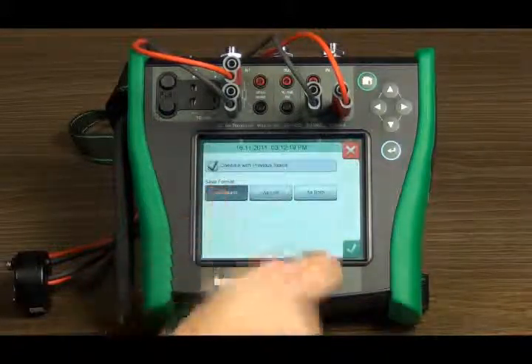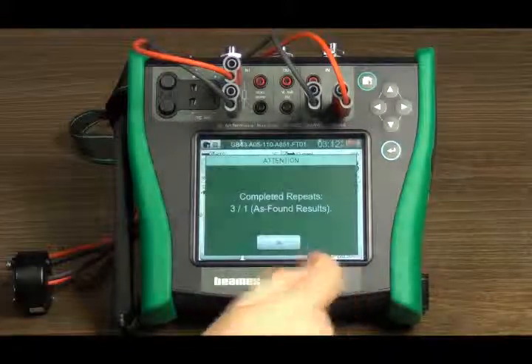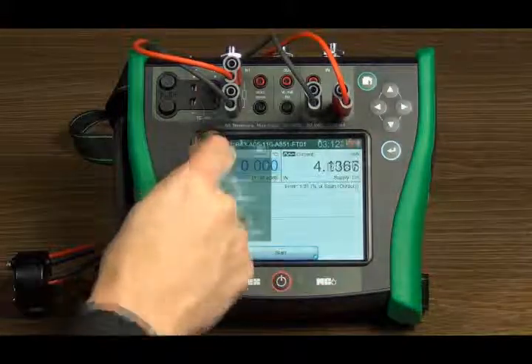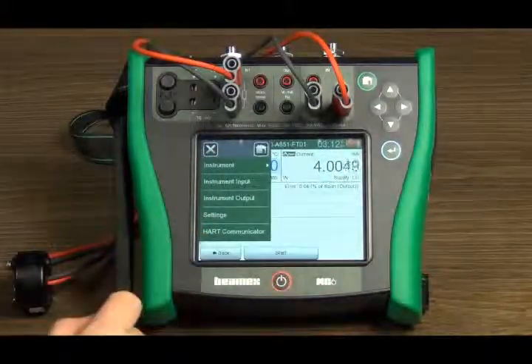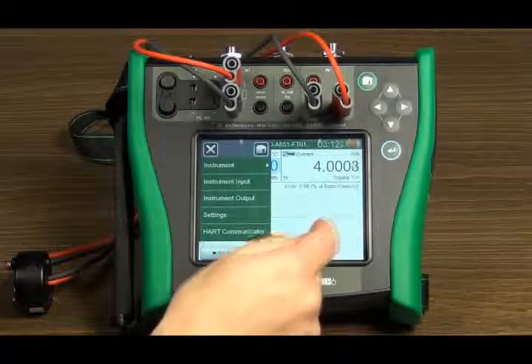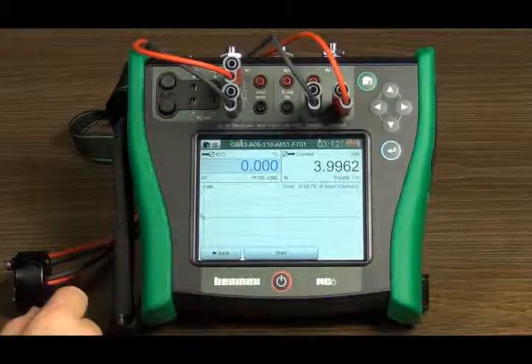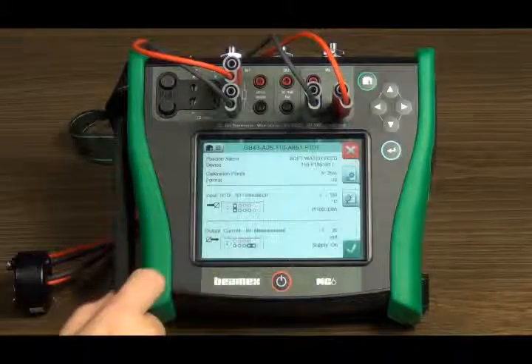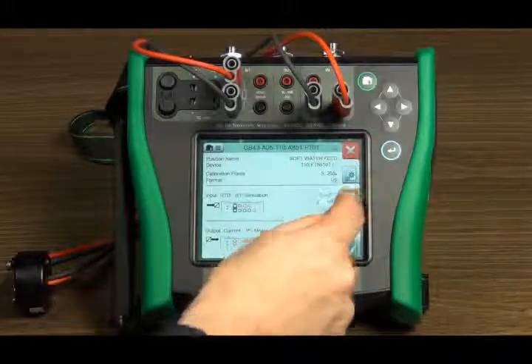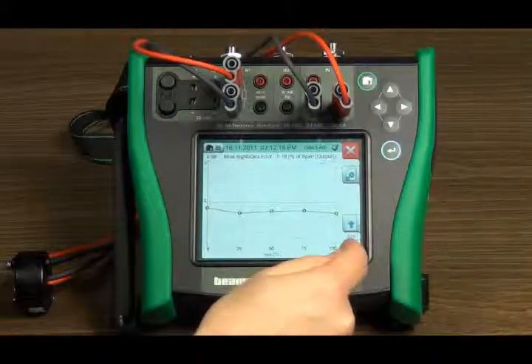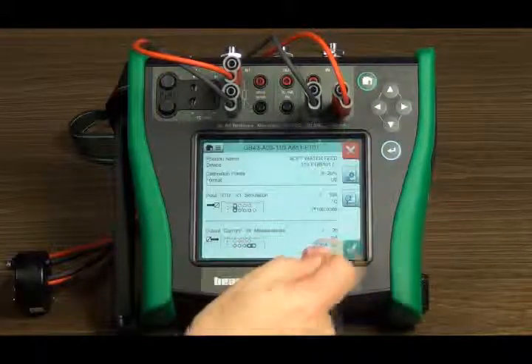If there was a need to adjust this HART transmitter, we can start the HART communicator from the menu. Please see the HART communicator video for more on that. Now the calibration is completed and the results are saved in the calibrator's memory. The results can be viewed in the calibrator and can also be uploaded to calibration management software.